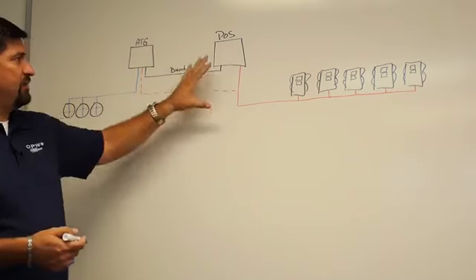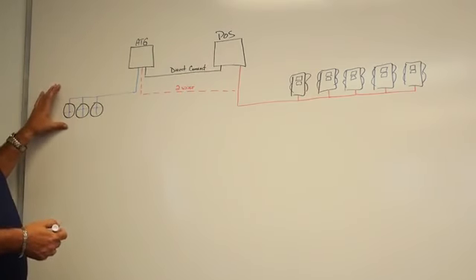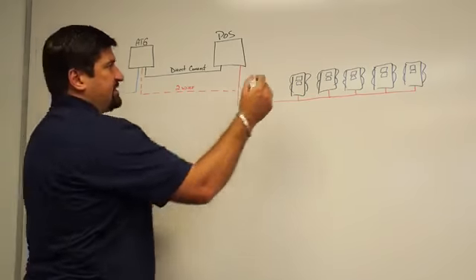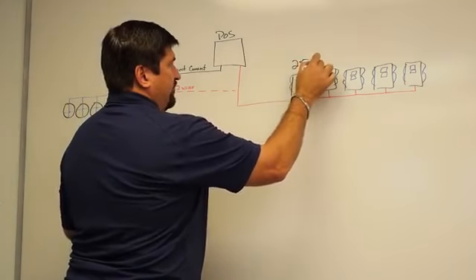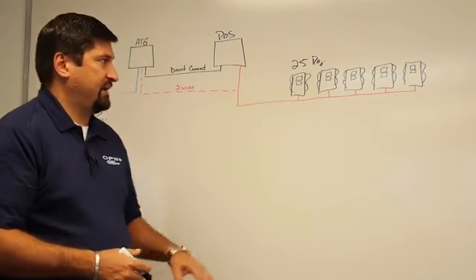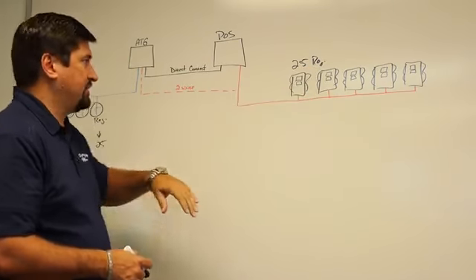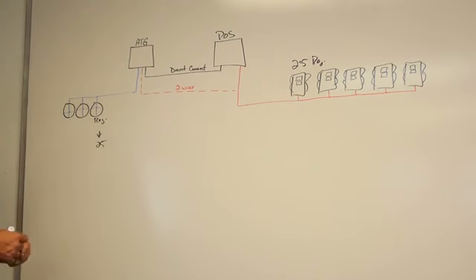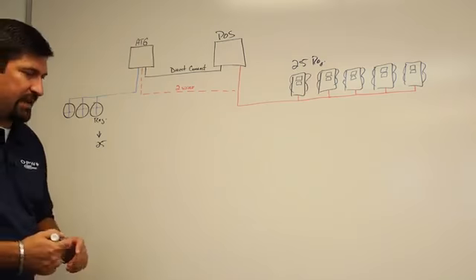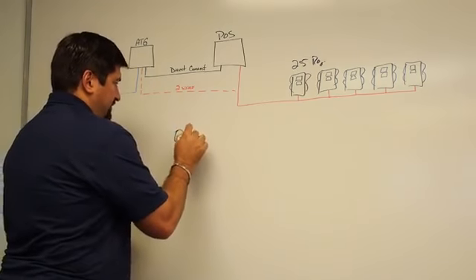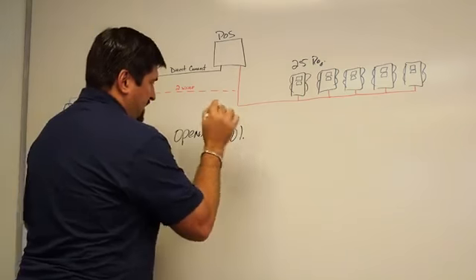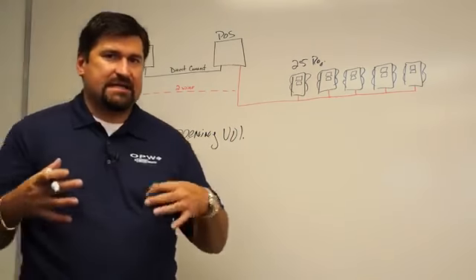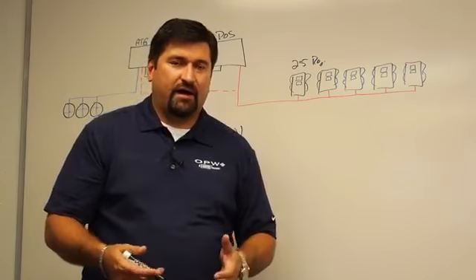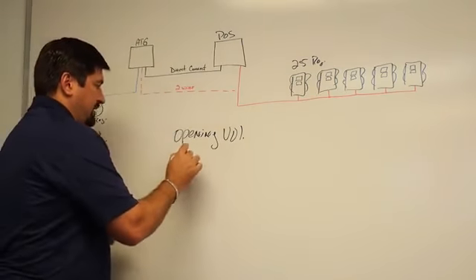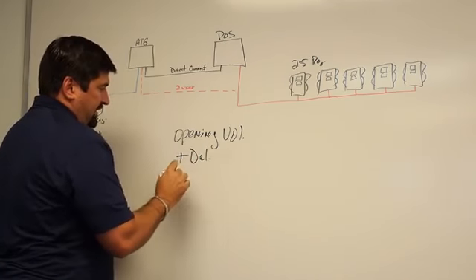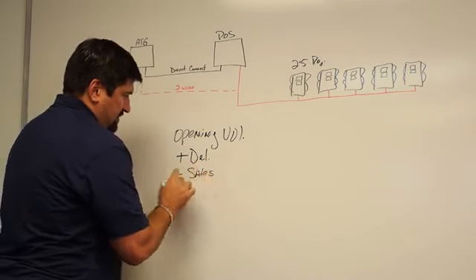Whichever way I communicate, I'm looking at the ATG and at the tanks that are at the site. So let's say this dispenser says that it pumped 25 gallons of regular. Once the dispensing activity is finished, I see that I pumped 25 gallons out of the regular, and I see that I got 25 gallons in the regular tank. So when I'm doing wet stock management, what I'm looking for is the opening volume. Opening volume is the actual physical volume that is in that tank at the beginning of the day.